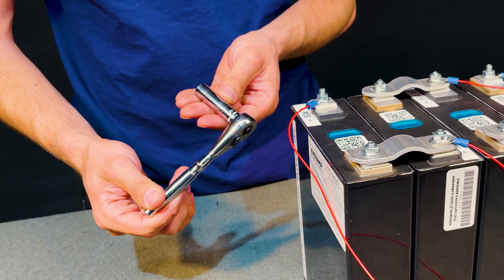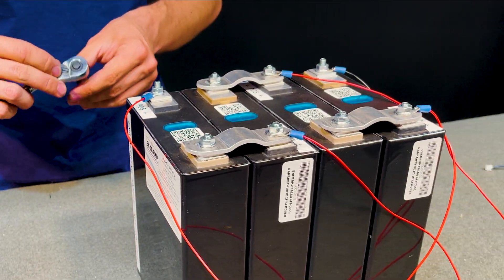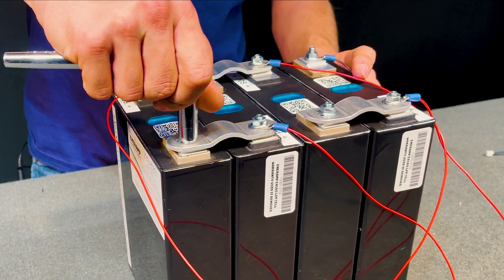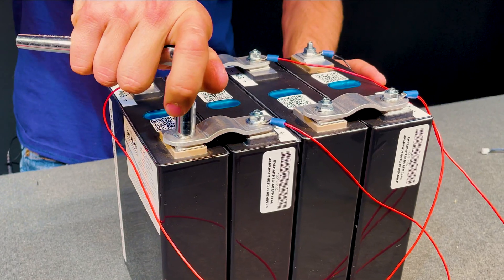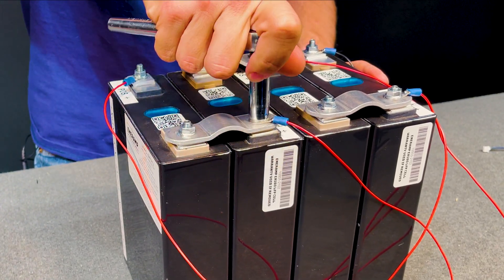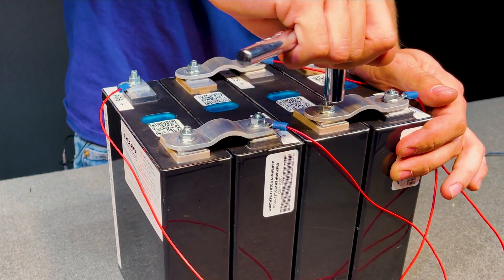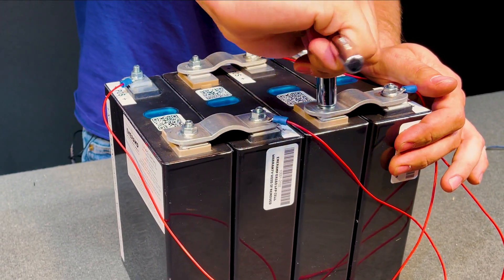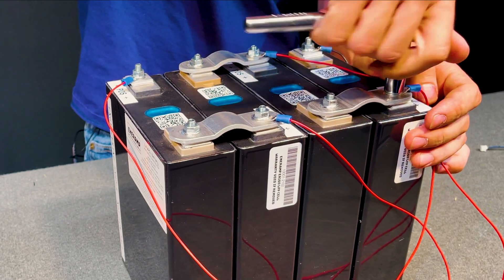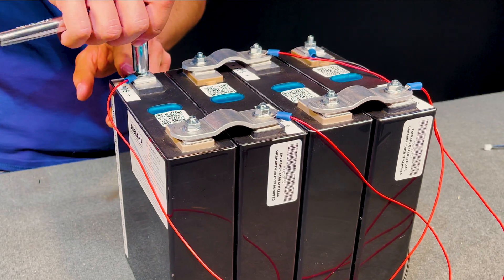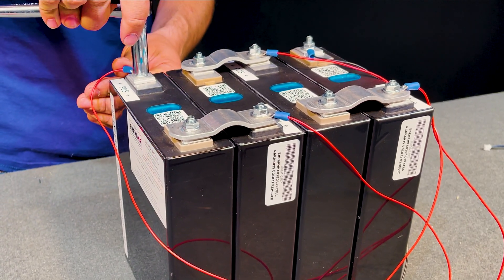Now using our 10 millimeter socket and quarter inch drive ratchet we can tighten down some of these terminals. I'm going to tighten down everything except for the main positive and main negative terminals. Ideally you would be using a torque wrench for this and meeting the torque specs of the batteries you are using. And we're going to get a little bit of snug tightening on the main terminals but not too much.